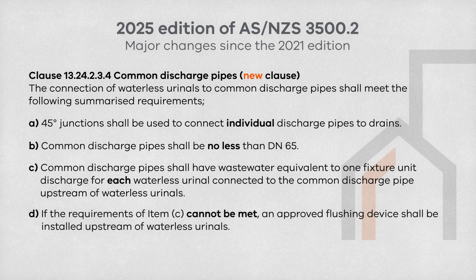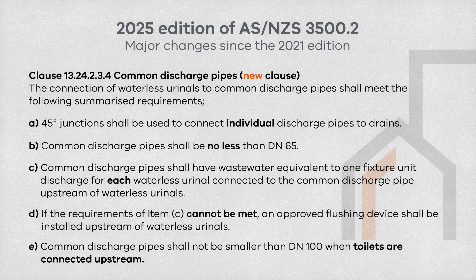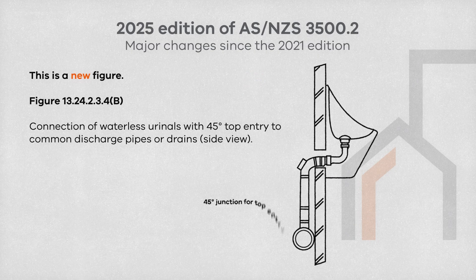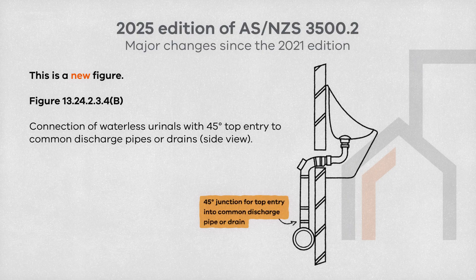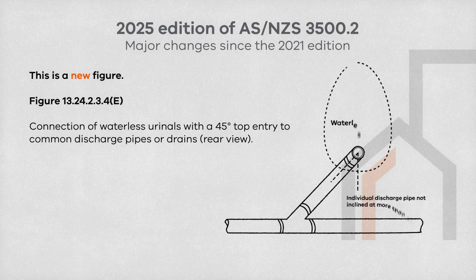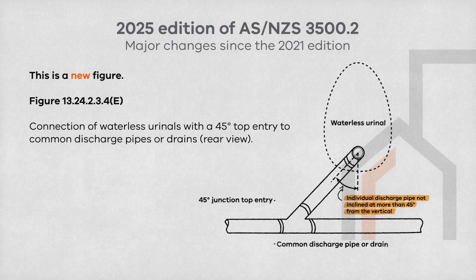If the requirement of item C cannot be met, an approved flushing device shall be installed upstream of waterless urinals. Fifth, common discharge pipes shall not be smaller than 100mm when toilets are connected upstream. New figures have been added showing the connection of waterless urinals with 45-degree top entry junctions to drains, and the connection of waterless urinals with 45-degree top entry to common discharge pipes.